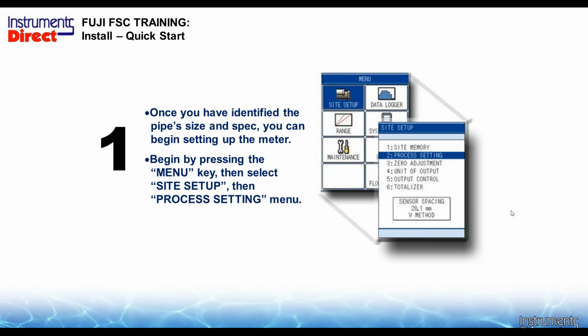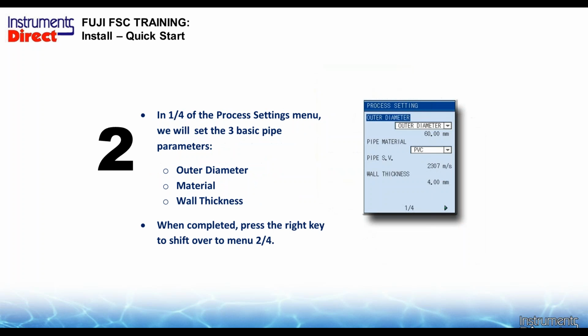So let's get started in programming this guy. And we're going to break it down very simple because it is very simple. So the things you need to do before you play the game here is you have to have a little bit of data. So you need to identify your pipe size, your pipe material, your process liquid, and then we can actually begin to program the meter. So to go here, you begin by pressing the menu key, then you select Site Setup, and then you select Process Setting menu.